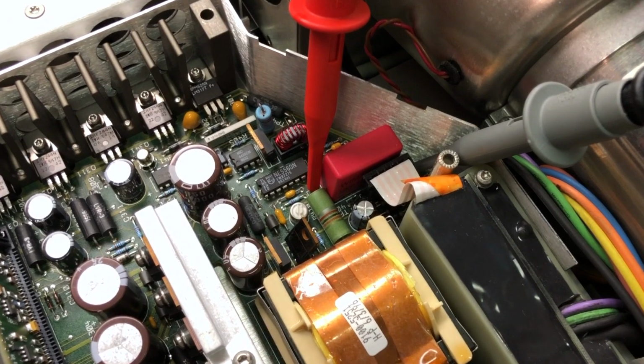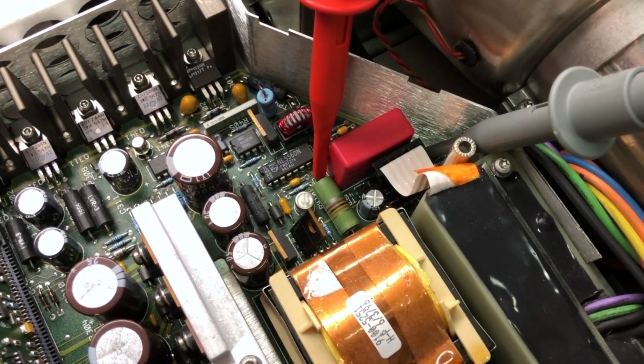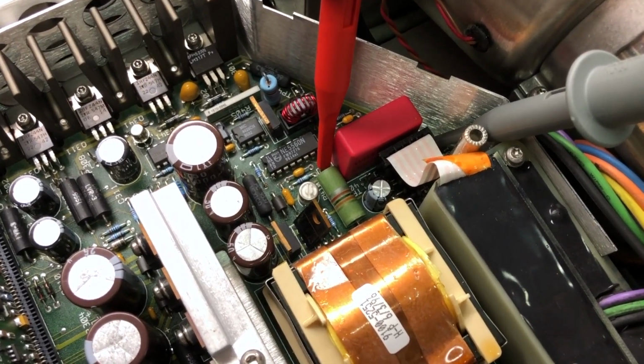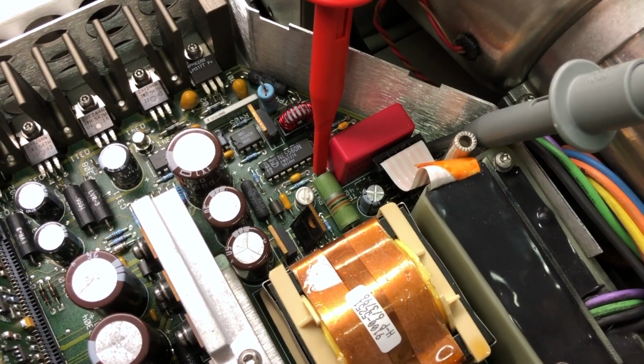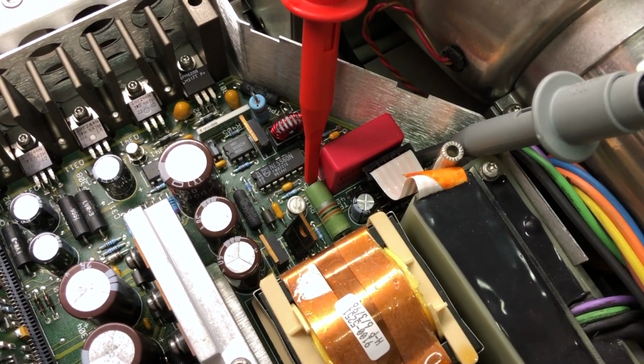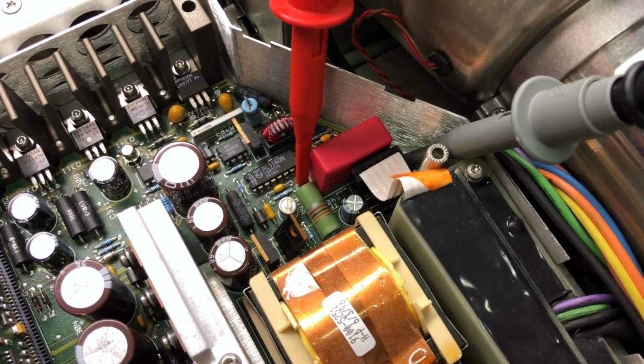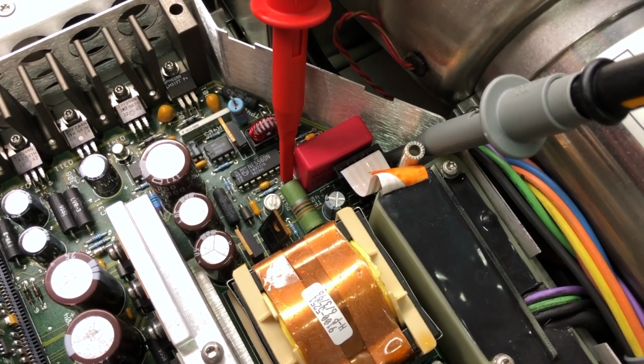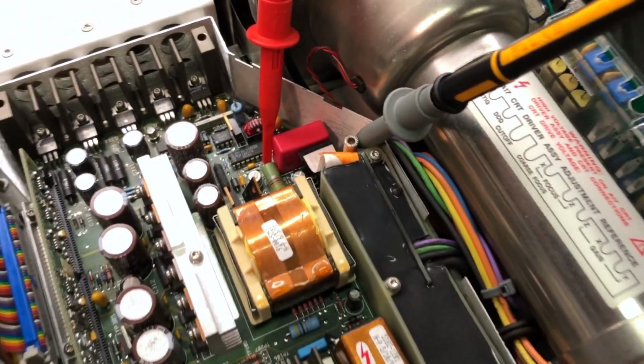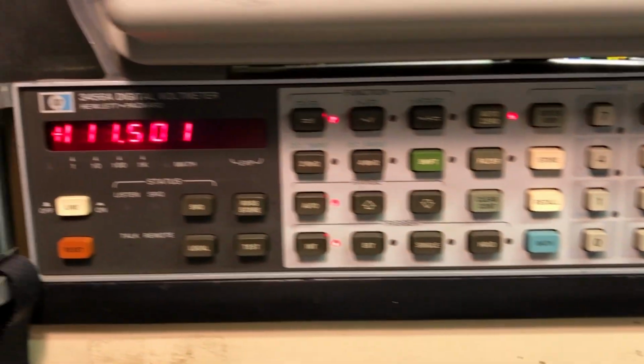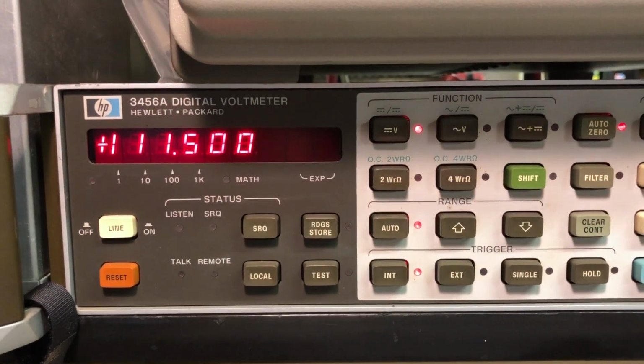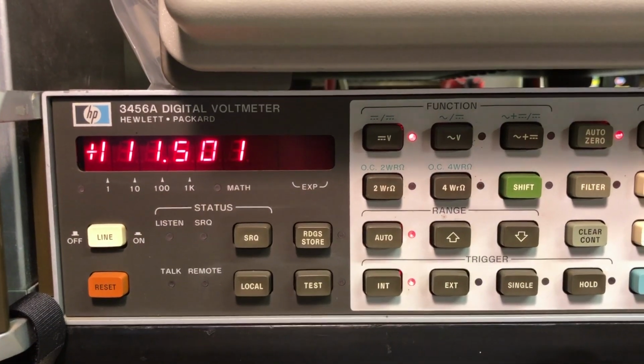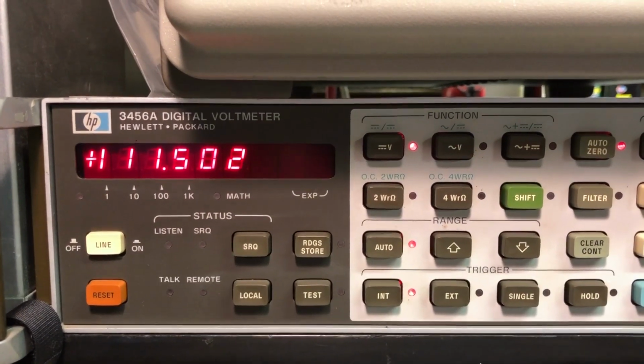You can see at the end of the red test probe down there, there is a potentiometer on the circuit board. That's the only adjustment in the power supply, and that needs to be dialed in to exactly the voltage that's on that label. So that is where it is set now. Originally it was reading a little bit high, about 111.9. You can see now it's dialed in to 111.5, so it's spot on.